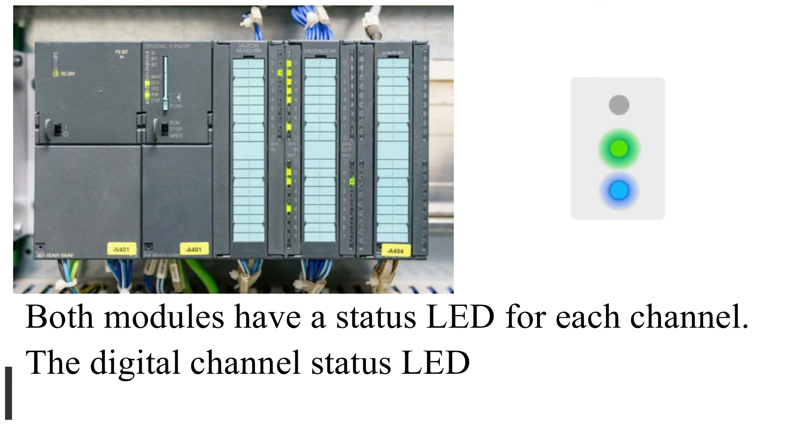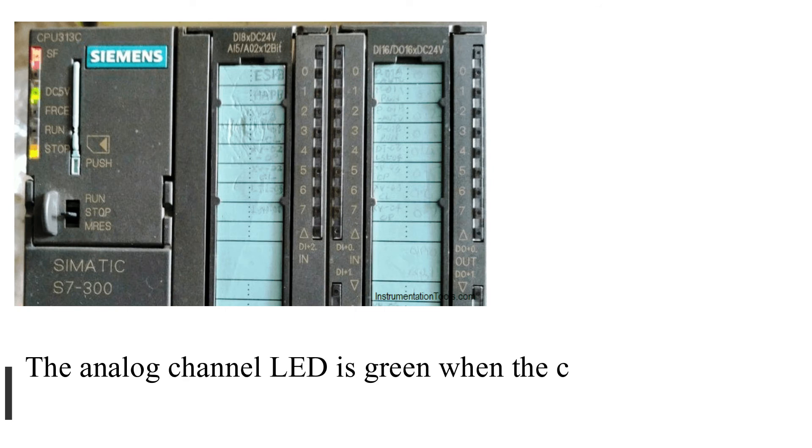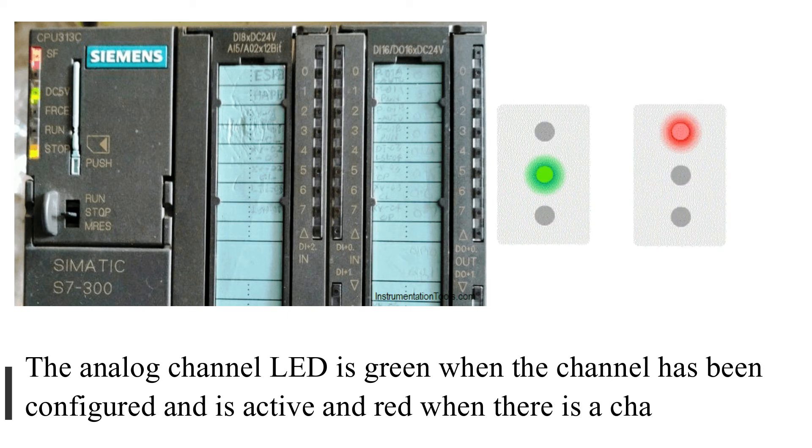The digital channel status LED is green and turns on when the input or output is on. The analog channel LED is green when the channel has been configured and is active, and red when there is a channel error.